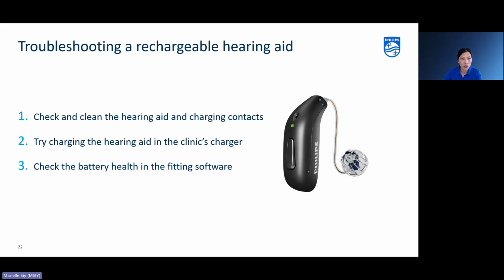The first one is you should start by checking and cleaning the hearing aids as well as the charging contacts on the hearing aids. Use a dry cloth. Sometimes they sweat a lot, sometimes there's oils, sometimes they even wear perfumes and all of these other lotions. So clean the hearing aid first. The second step is once they're clean and functioning, so the hearing aid turns on and there's sound coming from the speaker, then they can try charging the hearing aids in your charger. It's always good to have your own charger in the clinic exactly for these troubleshooting scenarios.